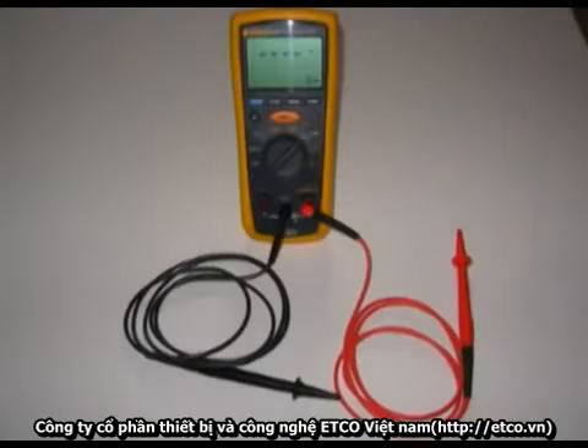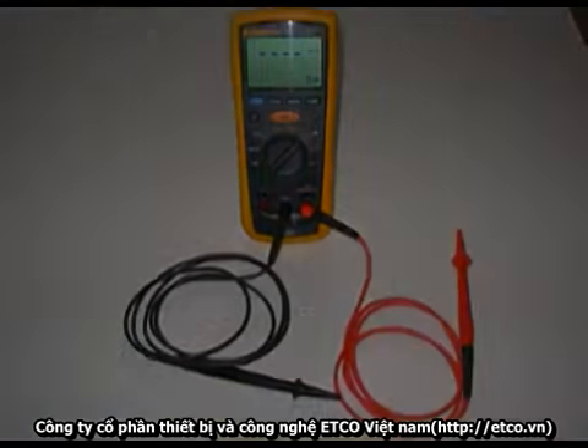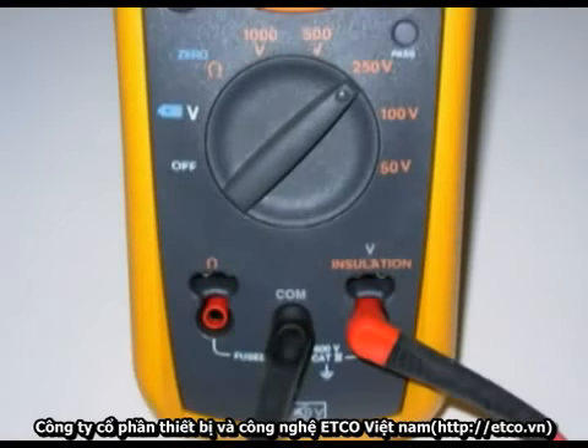See, we've got the standard test leads installed, and here the meter is set on 500 volts to do an insulation test. That voltage will be applied for as long as you press the test button, or it'll be applied automatically for 1 minute, or 10 minutes if the PI or the DAR position is selected. This shows a receptacle for either the standard or the remote test leads. You might also notice that this is a Cat 4 meter and it's rated at 600 volts.